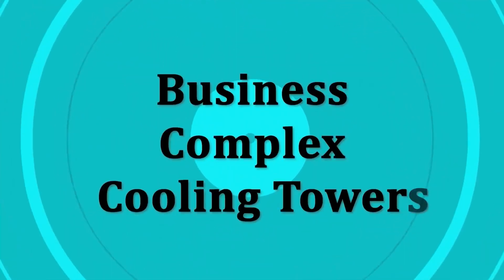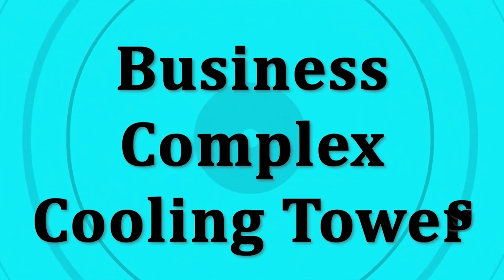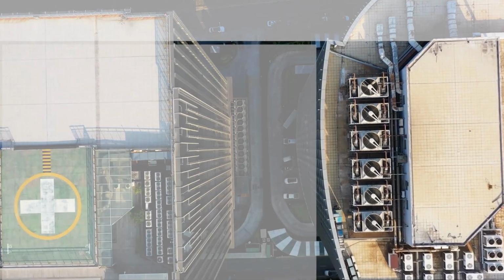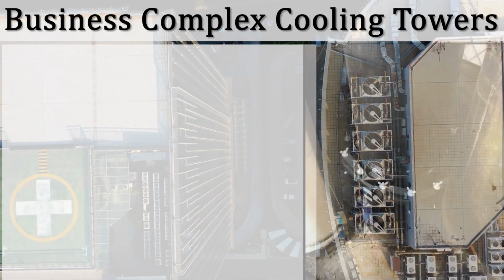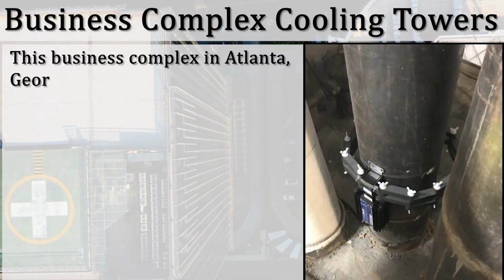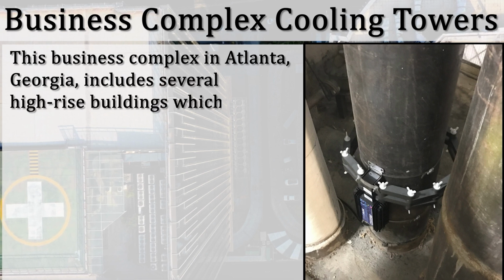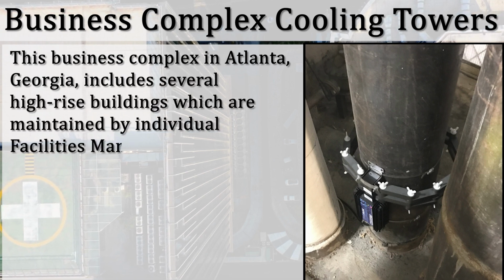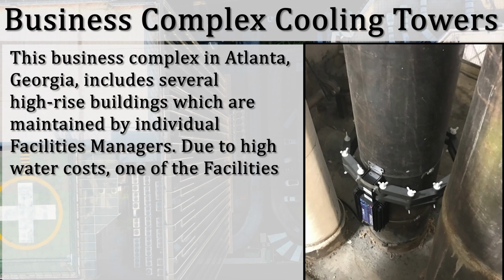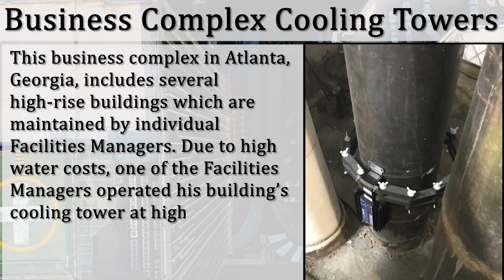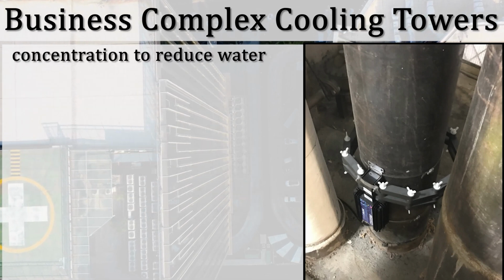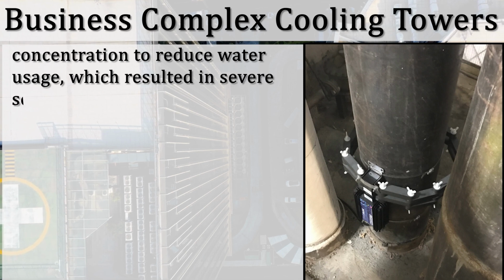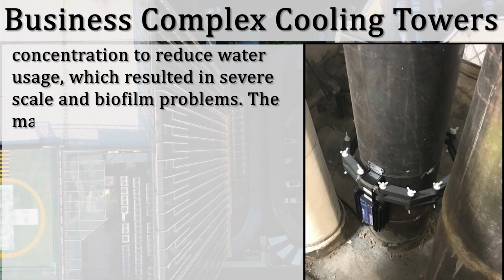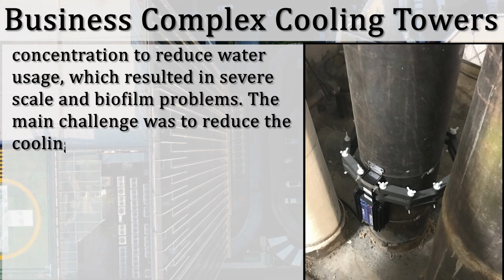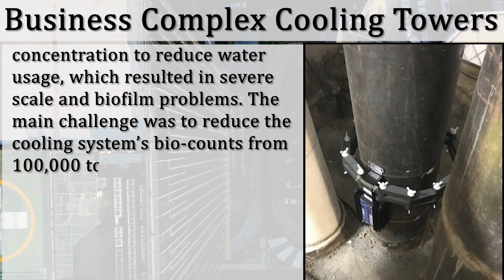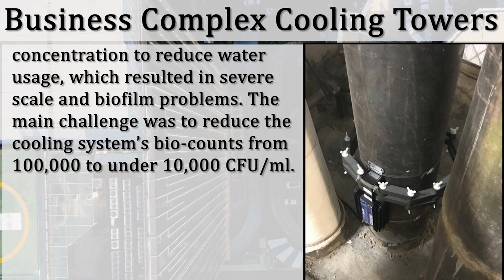Business complex cooling towers. This business complex in Atlanta, Georgia includes several high-rise buildings which are maintained by individual facilities managers. Due to high water costs, one of the facilities managers operated his building's cooling tower at high cycles of concentration to reduce water usage, which resulted in severe scale and biofilm problems. The main challenge was to reduce the cooling system's biocounts from 100,000 to under 10,000 CFU per milliliter.